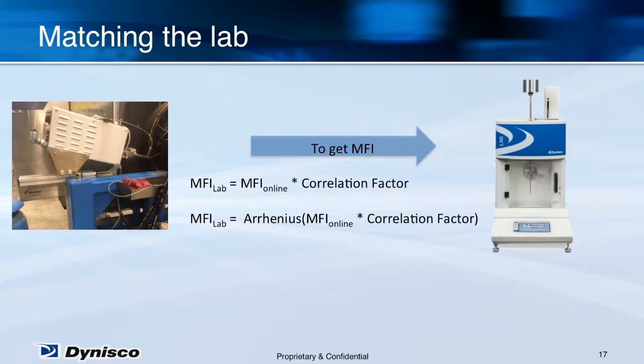That may not be practical given the residence time required for the material to stabilize to lab temperature. Another solution is to add a correlation factor that is simply the ratio of the lab and online results. A lot of customers do this. The only downsides I see is that the correlation may need to be reset anytime the process temperature changes, and that it just feels wrong to me, like you simply added a fudge factor that makes a significant change to the reading just to make things work out.